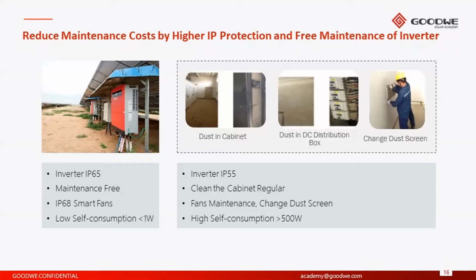the technology itself is not rated as IP65, but needs to be installed in some kind of control cabinet, or usually now manufacturers are supplying containerized solutions where all the components of the inverter are installed within a 20-foot or 40-foot container. There is a higher degree of maintenance associated with a large centralized inverter, and not only the maintenance, but also a higher degree of knowledge or expertise is needed to maintain the centralized solution over time.